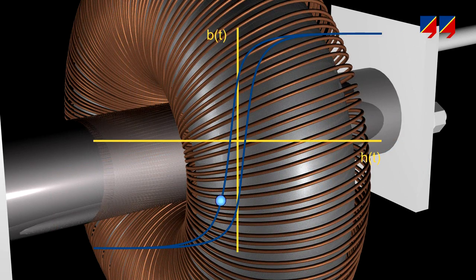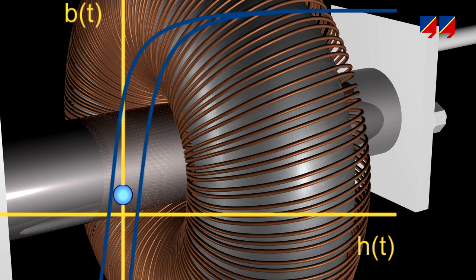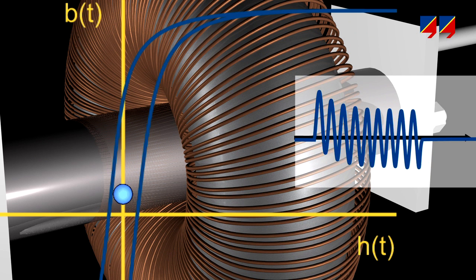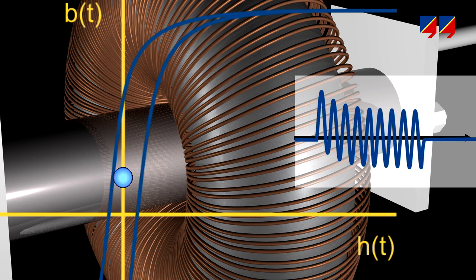A critical situation arises if a CT core has high magnetic remanence from a previous fault, and then a subsequent short-circuit fault occurs. This is exactly what happens in line protection schemes during an auto-reclosure cycle.